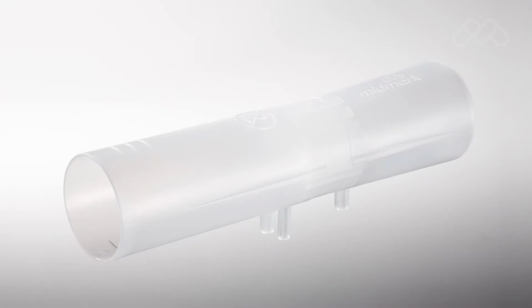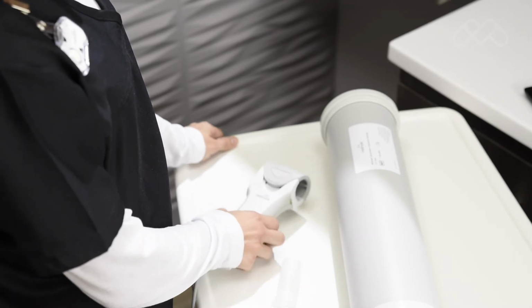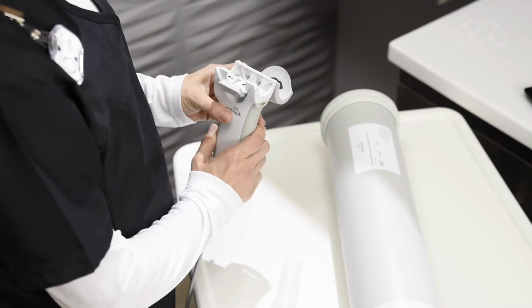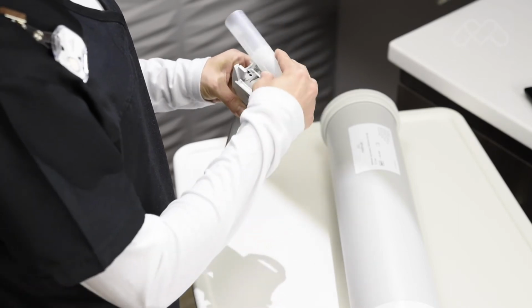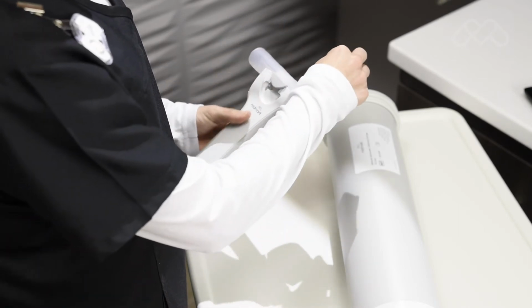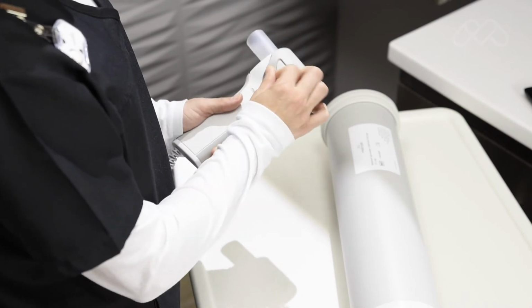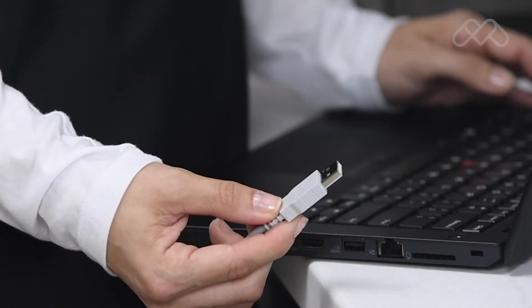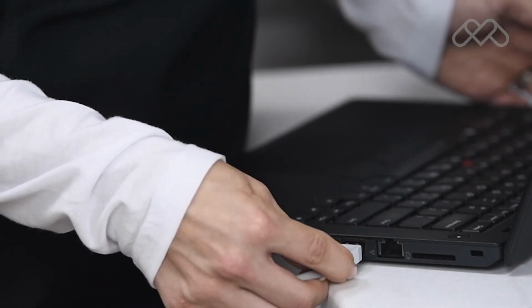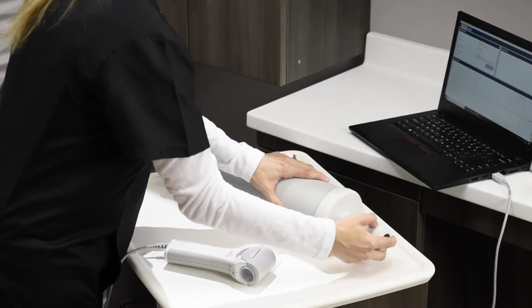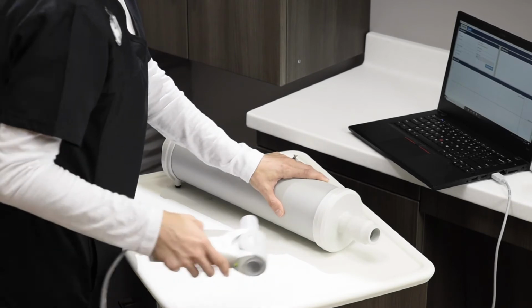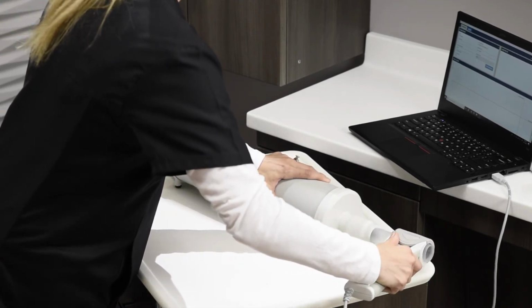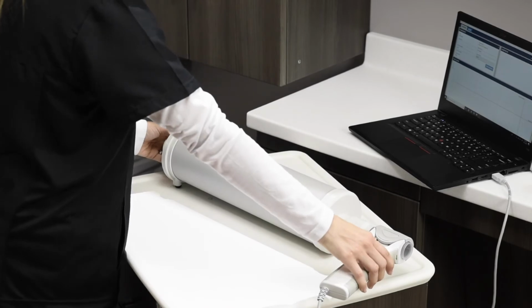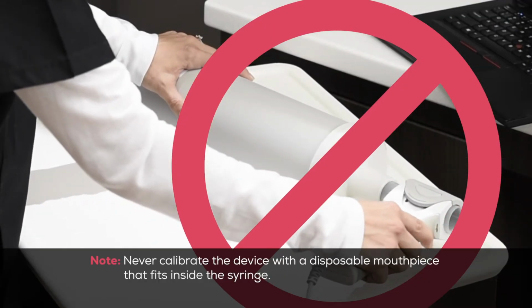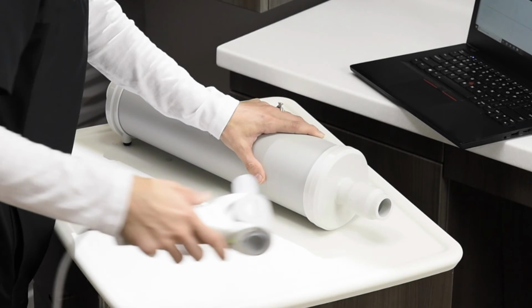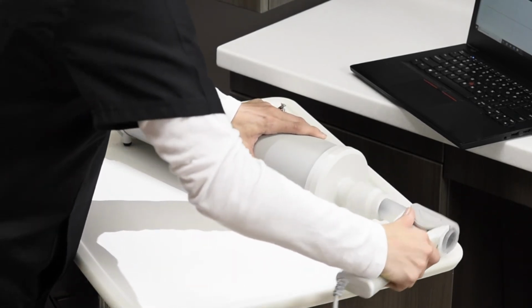Using a disposable mouthpiece, open the door to the digital spirometer and align the pins of the mouthpiece with the ports in the device. Press the mouthpiece into the ports. Then, close and latch the spirometer door. To set up the spirometer for calibration, connect the device USB into the computer. Attach the large end of the syringe adapter to the calibration syringe and the small end of the adapter to the disposable mouthpiece that is attached to the spirometer. Be sure to always use the syringe adapter when calibrating the spirometer.